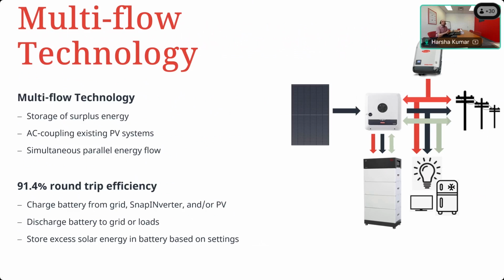Previously, the Primo 10s without the Gen24 - the regular string inverters - if hydro was down, the inverter would be down too, because those were grid-following inverters: no grid, no inverter. Whereas now, since this is a hybrid inverter, let's assume that with the Gen24 you've got a battery stack and hydro is down. The Gen24 makes its own grid because it's a hybrid inverter.